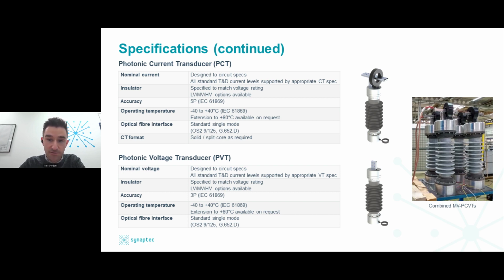So here you can see some of the specifications of the PCT and the PVT, the current and voltage transformer. Both of these can address all standard transmission and distribution current and voltage levels by selection of the appropriate primary transducer. The image on the right shows some 33 kV combined current and voltage sensors, which have recently been manufactured and are under test. And again, both of these employ standard single mode telecoms fiber. So this, along with the use of standard CTs and VTs, is why the devices are so straightforward to install. Installation can be performed without any specialist skills beyond those that already exist in the sector. That's basically mounting of the instrument transformer and standard telecoms fiber splicing. So there's nothing terribly unfamiliar to installers in the sector, which is what makes these so straightforward to put in place. So that's a very, very quick overview of how the technology works.